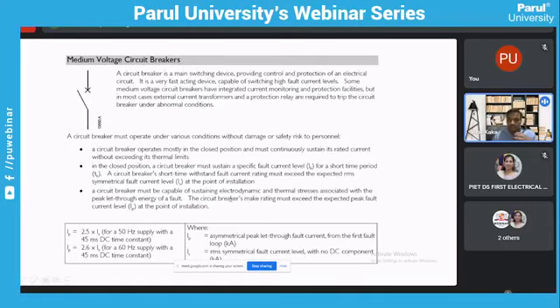Now, as we all know, medium voltage circuit breakers are switching devices required to clear a fault as fast as possible. This presentation gives an overall brief idea of what circuit breakers are, and that they are required to clear faults as fast as possible. They are required to have integrated current monitoring and protection facilities as well. But in most cases, an external current transformer and protection relays are required to trip the circuit breaker under abnormal conditions. Whenever there is a fault inception or fault initiation on the circuit, it triggers and then passes through to open the circuit breaker.